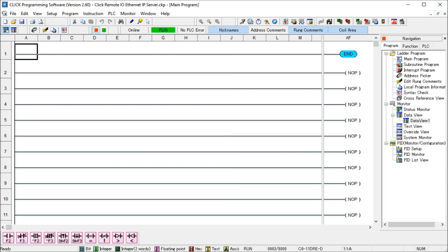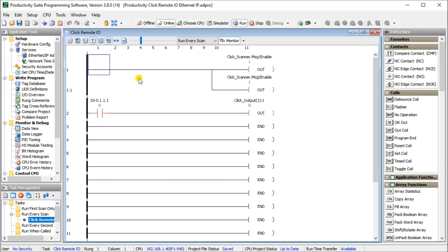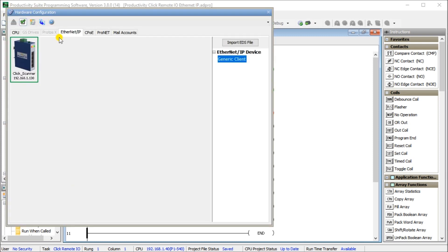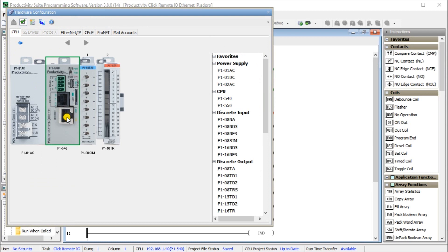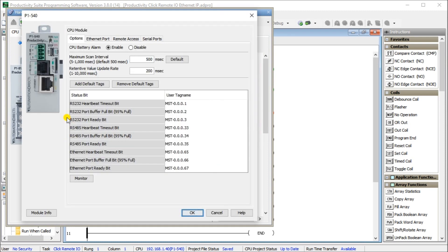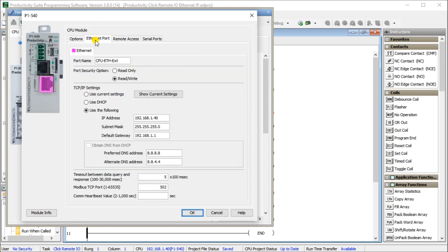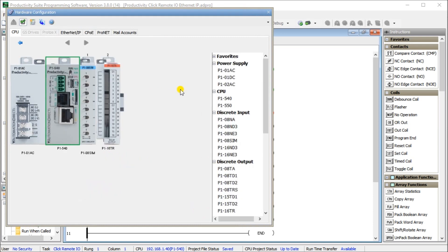Now let's call up our Productivity software. Under the Productivity software we'll go to Setup, Hardware Configuration, and look at our CPU first. Under the CPU we'll look at Ethernet and double-click the port on the CPU itself. We'll hit the Ethernet Port tab and you can see that again we've set up a static IP address. It's important to use static IP addresses with a fixed network. Our address is 192.168.1.40 with subnet mask 255.255.255.0, which matches exactly what the Click had.